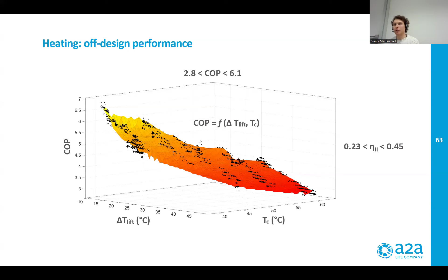The purpose was to obtain one function like the one that you can see in this slide, where the COP is represented as a function of the temperature at the condenser and the temperature difference between the condenser and the evaporator. And you can see the COP values that are in the range between 2.8 and 6.1. Obviously, reducing the temperature at the condenser and decreasing the temperature difference between the condenser and the evaporator, the COP values increase, and so the performance of the prototype is the best.